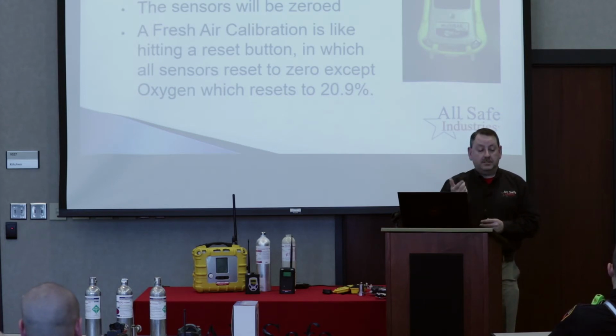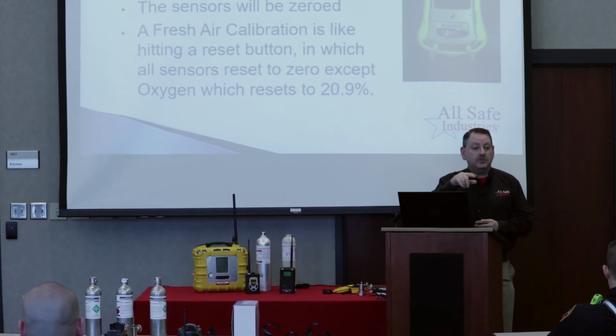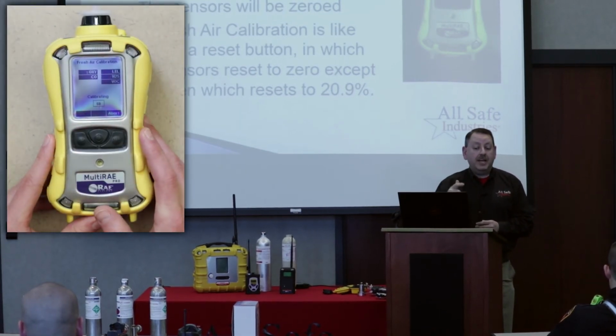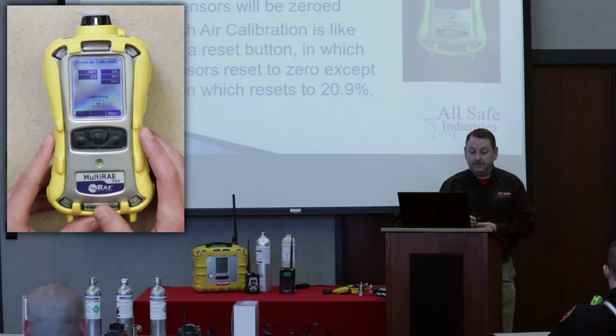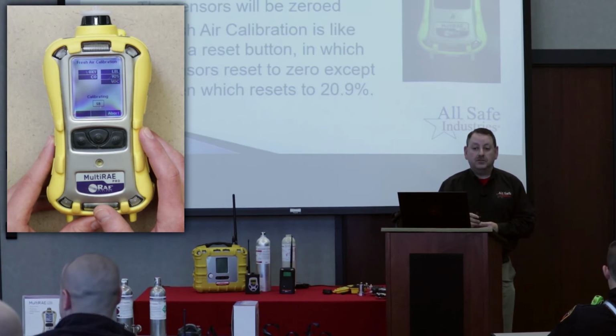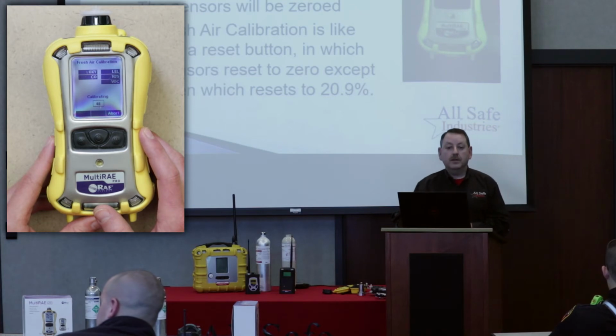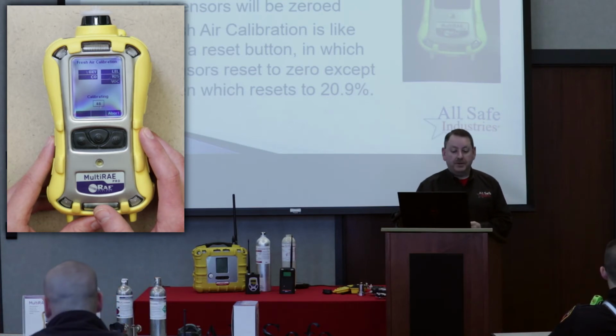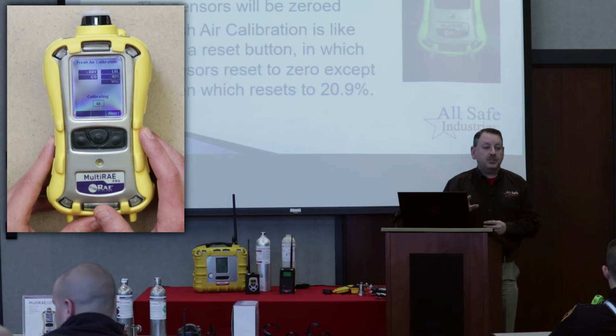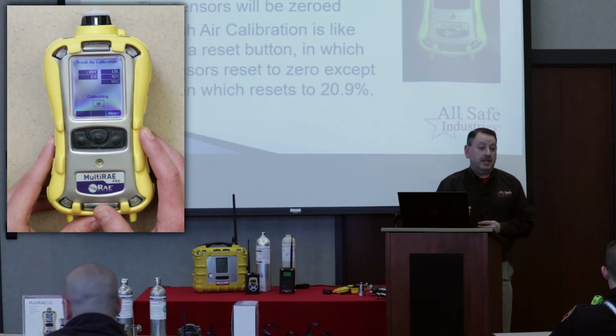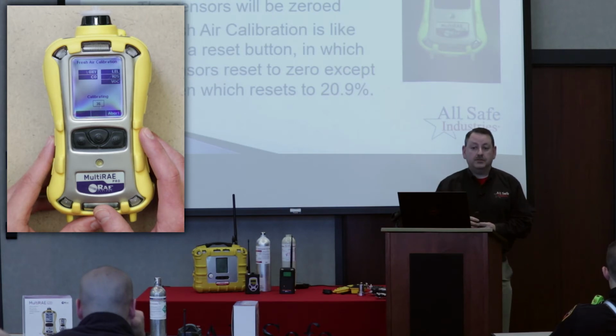So you want it to ask you for the fresh air calibration, just to remind you that that's the step you want to do. So everybody else go ahead and say start for that, and it's going to start a 60-second countdown. So make sure you're in clean ambient air. You'll press the start button, and this will zero out all the sensors. They'll all read 0 except for which one? The oxygen, and it will read 20.9. So think of a fresh air calibration like hitting a big reset button. You're just telling the meter, hey, you're in fresh air, reset all the sensors, okay?